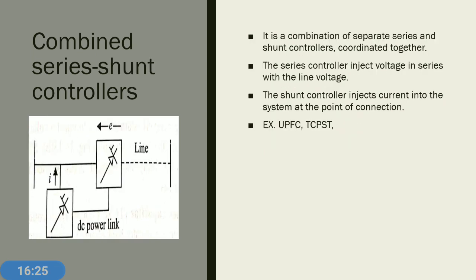The last type is the combined series-shunt controller, which combines a shunt controller injecting current and a series controller injecting voltage, working in a coordinated manner to control transmission line parameters. The series controller injects voltage in series with the line and the shunt controller injects current into the system at the point of interconnection. Examples include UPFC (Unified Power Flow Controller) and TCPST (Thyristor Controlled Phase Shifting Transformer).